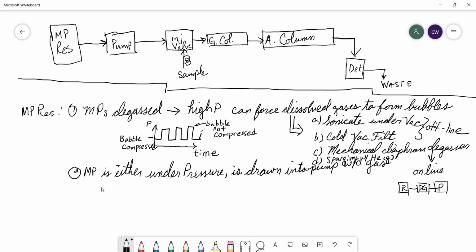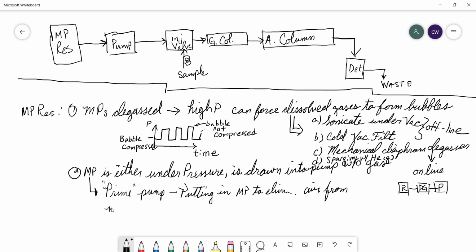So the other half of this is that we either have to be able to prime the pump physically, or we keep the mobile phase under pressure, okay, to assist us in pump priming. Okay, so this allows us to prime our pump. All right, which is putting mobile phase into the pump to eliminate air from the mechanics. Okay, so we have to push all the air out.